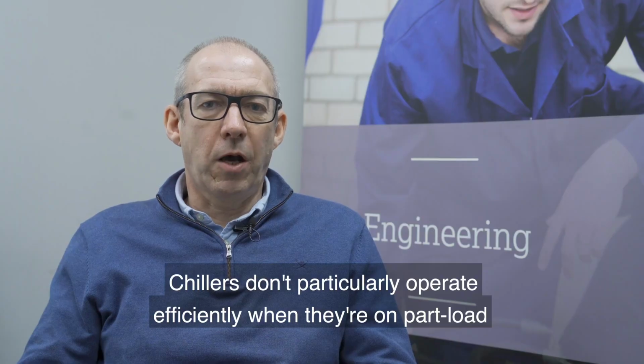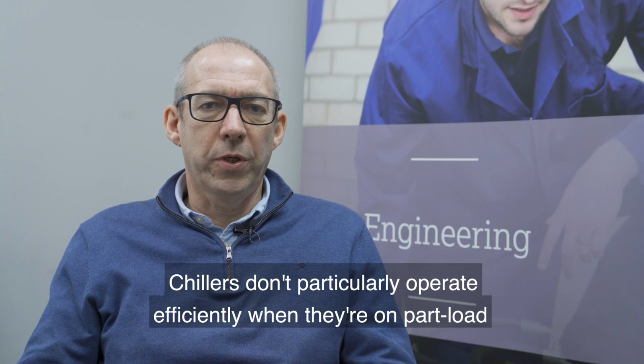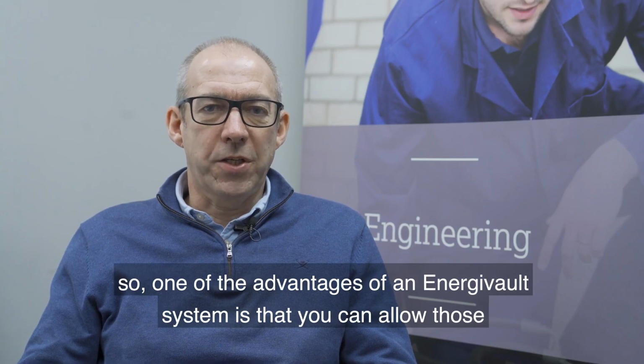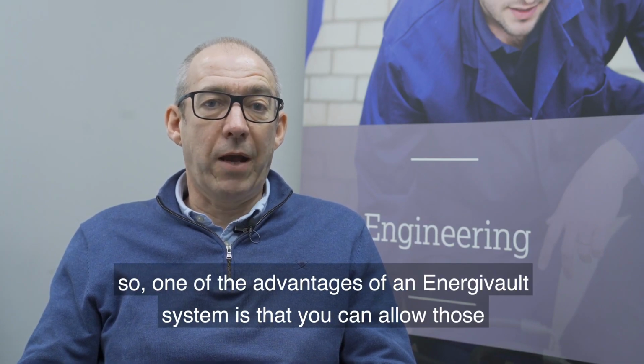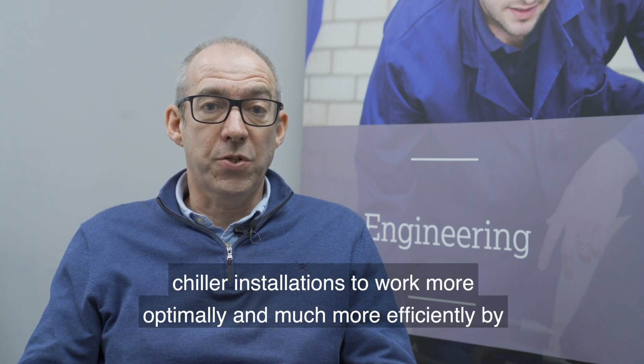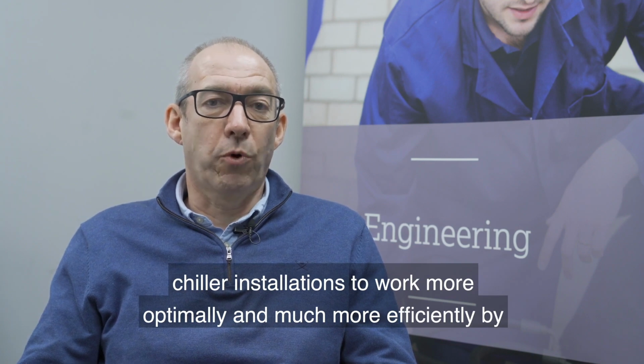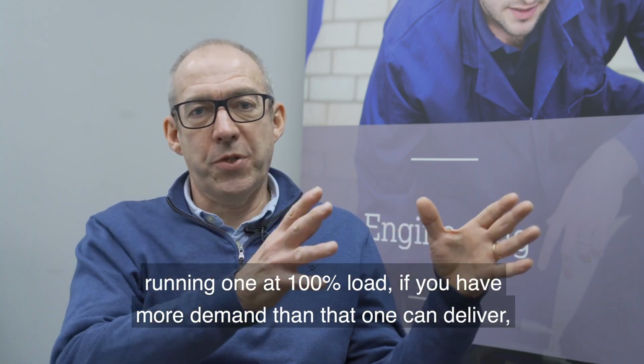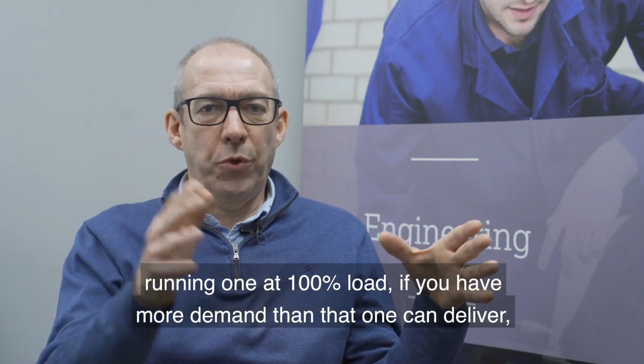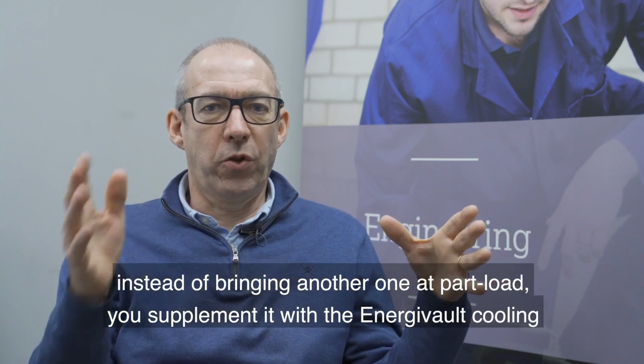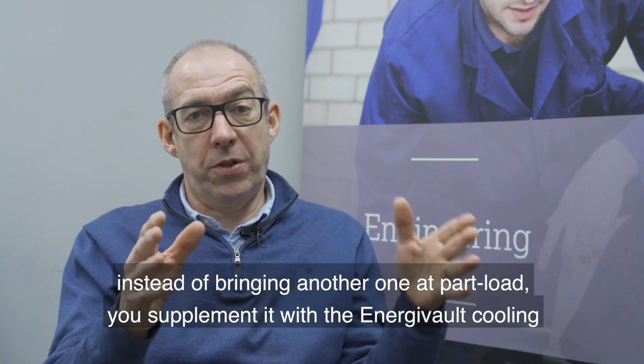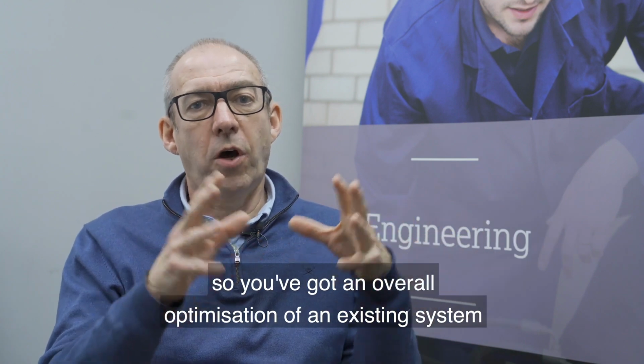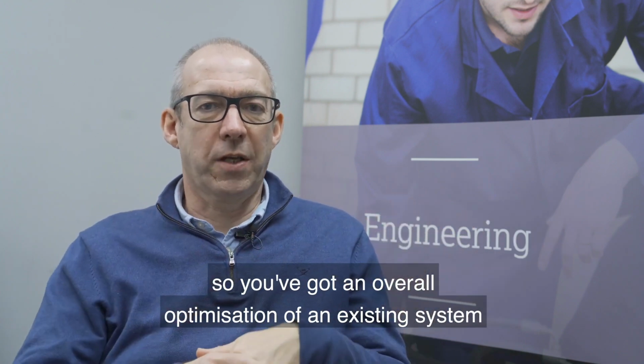Chillers don't particularly operate efficiently when they're on part load. So one of the advantages of an Energivault system is that you can allow those chiller installations to work more optimally by running one at 100% load. If you have more demand than that one can deliver, instead of bringing another one online at part load, you supplement it with Energivault cooling. So you've got an overall optimization of an existing system.